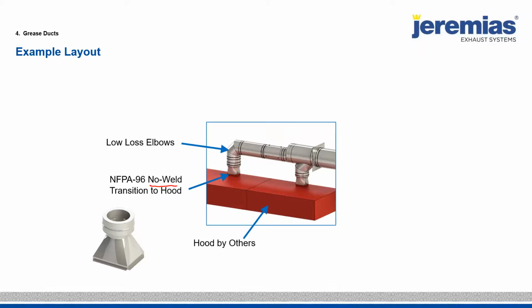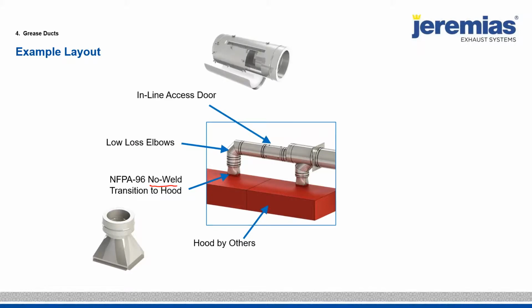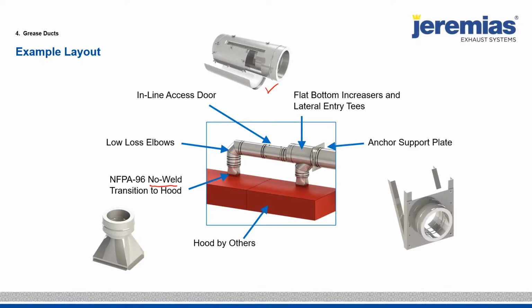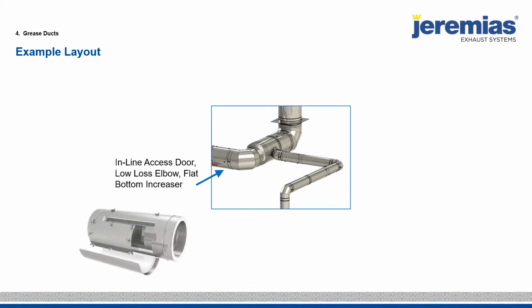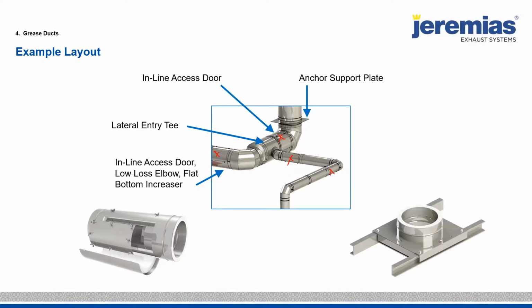We like to use low loss elbows. Our access panels are very easy for us to make. We have 3D laser technology, so we can make these for almost next to the cost of a straight pipe length. So we actually have a lot of inline access panels with our style of grease duct systems. All the supports, hangers are taken care of. Again, this illustration right here has an access panel here, here, here, and there. So you have actually 4 access panels, and then the vertical support of the stack is provided by the factory also.